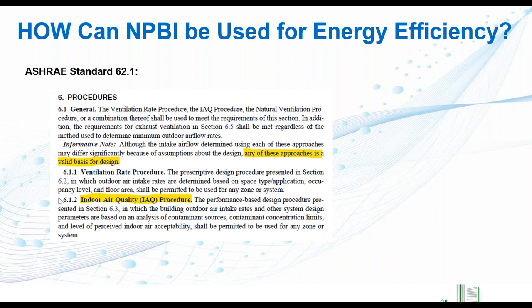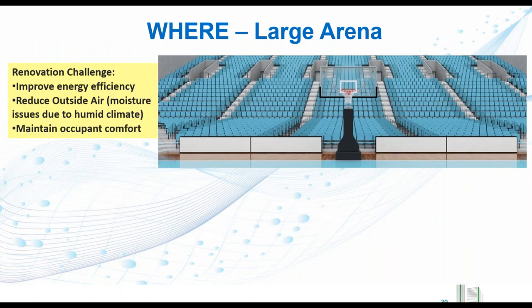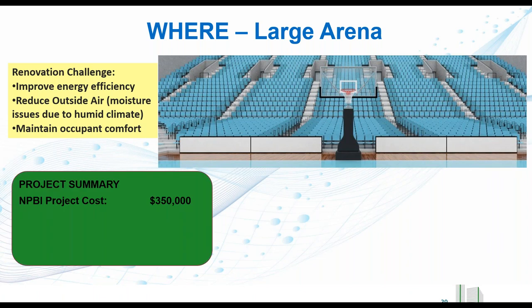So let's talk about a couple of examples of where this has been done to show some energy savings. This is a large arena down in Tampa, and the renovation challenge was to improve energy efficiency and reduce outside air because we had moisture issues due to a very humid climate, all while maintaining occupant comfort. The needlepoint bipolar ionization equipment part of the project cost was $350,000. This was part of a larger project. There's chiller replacement, controls upgrade, a lot of other things that occurred. The needlepoint bipolar ionization component of it was $350,000. Because the outside air was able to be reduced, there were reductions in chiller size, chiller pumps, chiller motors, to the tune of $1 million.